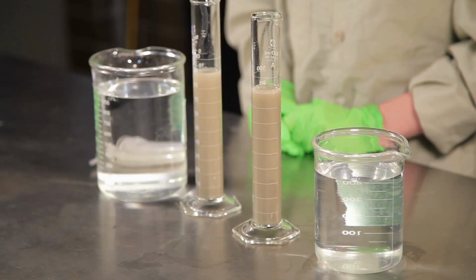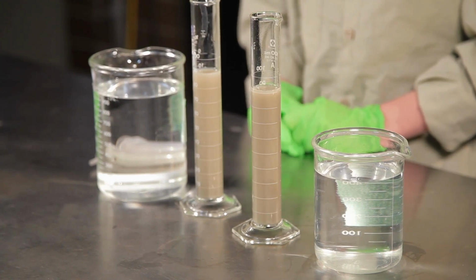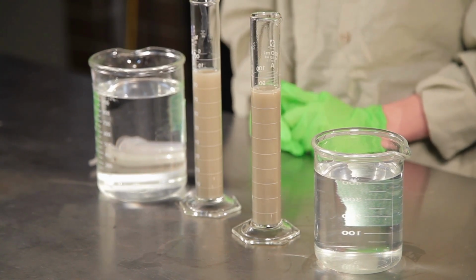To improve the settling behavior, we need to coagulate the fine particles. This will allow the fine particles to come together and form small agglomerates. Sometimes we can do this by changing the slurry pH to reduce the strength of the repellent forces between the particles. Sometimes this can be done by increasing the conductivity of the slurry. Another way coagulation can be achieved is by changing the surface charge of the particles by adding a polymer coagulant.